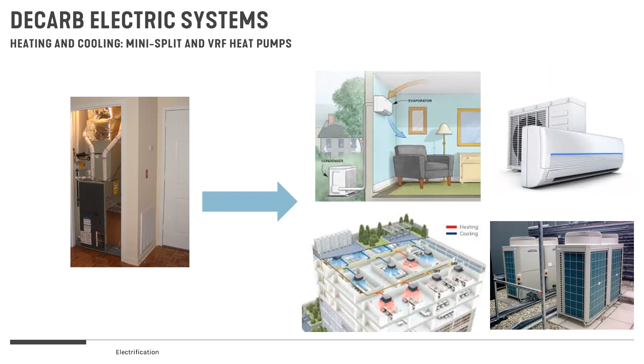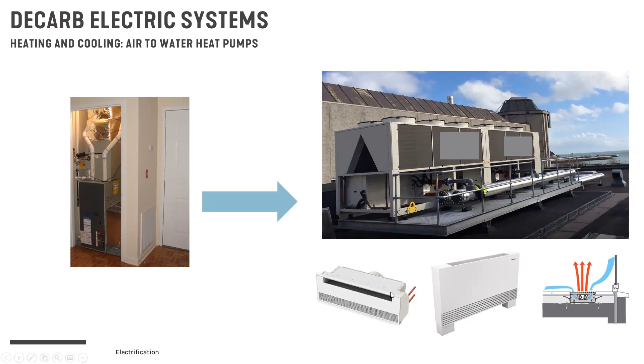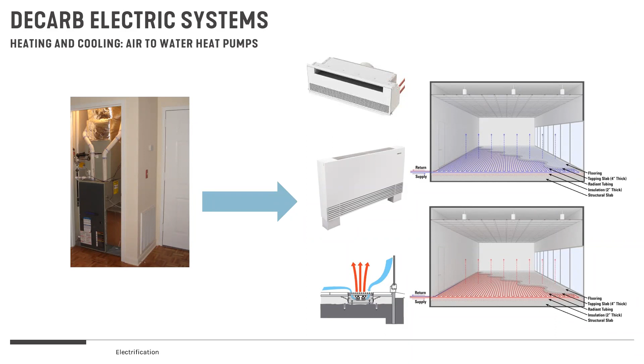On big commercial buildings, we're seeing a big push to go to what we call air to water heat pumps. These systems take air from outside, run it through a heat exchanger, steal that heat out of the air, compress it, and put it into water. We can pair those systems with all sorts of fan coils, chilled beams, and other things we'll talk about next week. We can also pair air to water heat pumps with radiant, so we can do radiant heating and cooling—one of my favorite systems. So a lot of options.